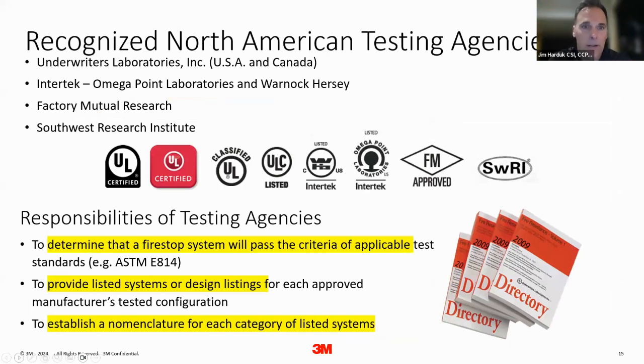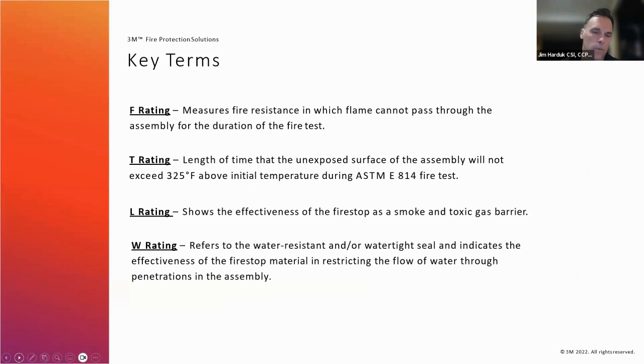And the testing is carried out by independent third-party labs. The most recognizable third-party lab is UL. I'm sure everybody's familiar with it, but there are others. There's Intertek, there's FM, there's SWRI. Basically, these third-party testing agencies' responsibility is to determine that a fire stop system will pass the criteria of the test application, ASTM E814. In addition to administering the test, they also have to document it. So they provide a listing number for each category, and each testing agency has their own nomenclature that they use to catalog all this information. Next slide. And I'll talk a little bit about that in a few slides here.